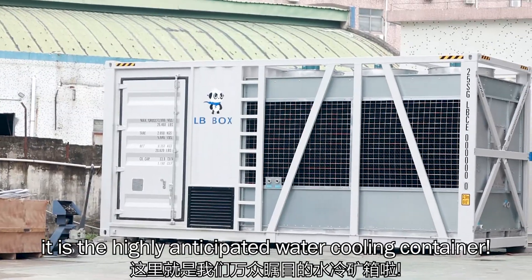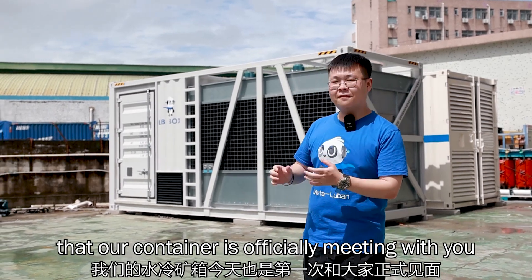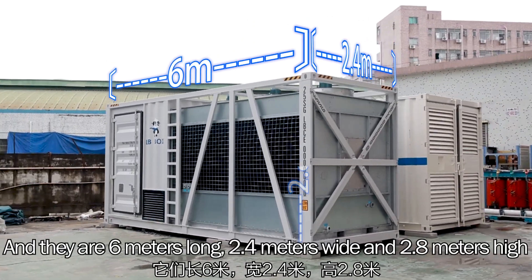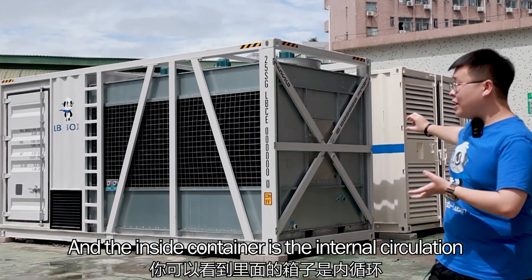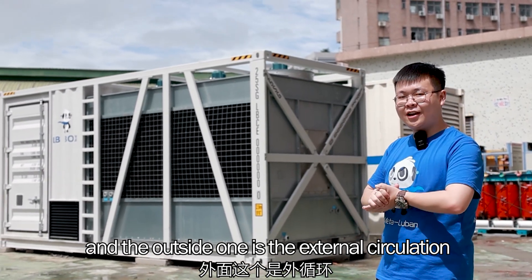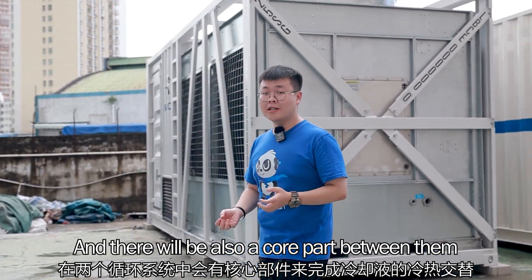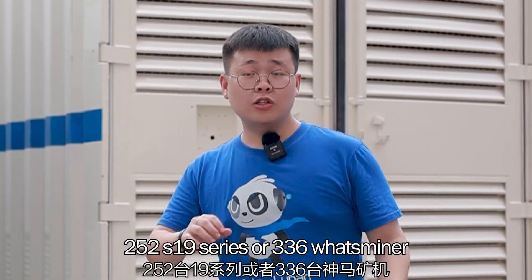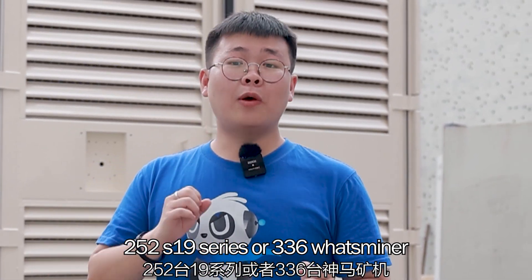Right here is the highly anticipated water cooling container, and it is also the first time that our container is officially meeting with you. As you can see, our container consists of two boxes and they are 6 meters long, 2.4 meters wide and 2.8 meters high. The inside unit is the internal circulation and the outside one is the external circulation, also the water cooling tower and the water curtain. There will also be a core part between them to complete the heat exchange. This container can hold 252 S19 series and 336 Whatsminers.